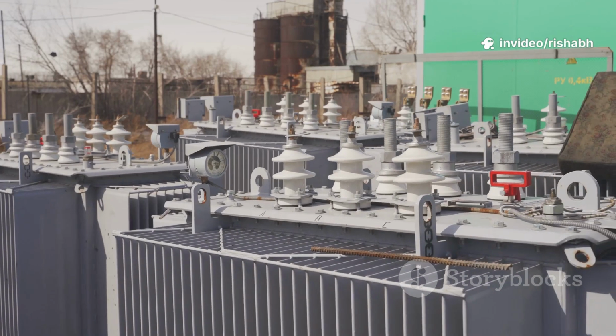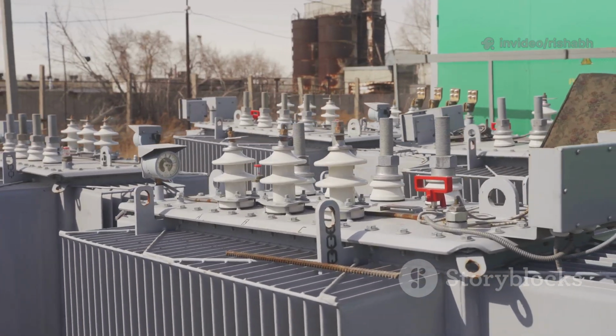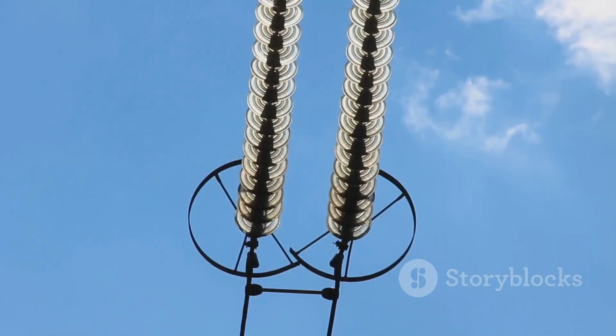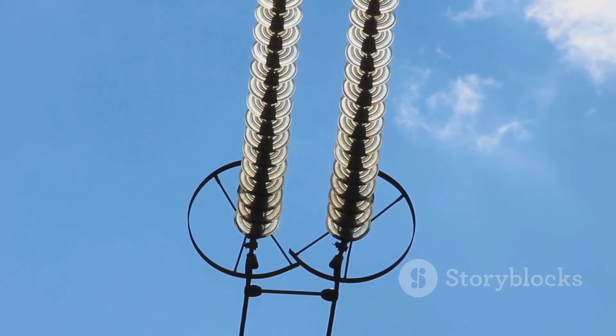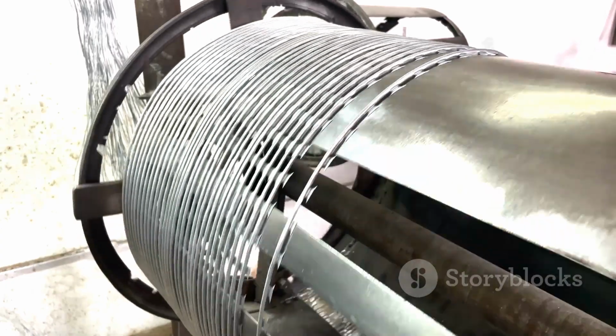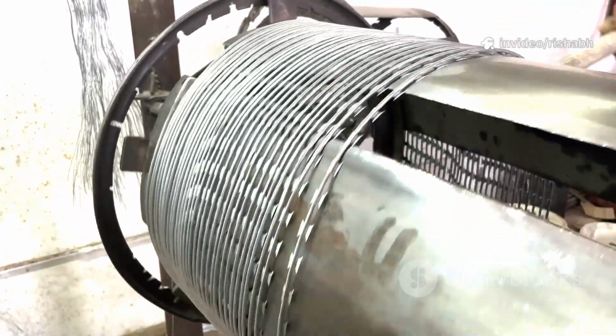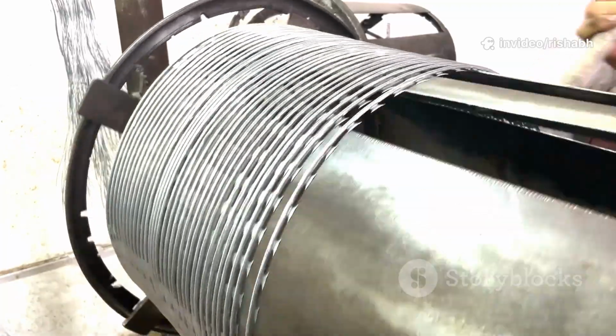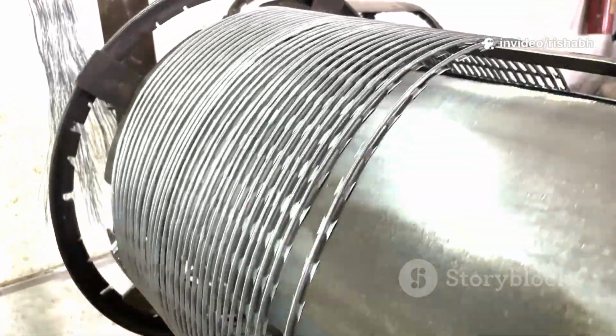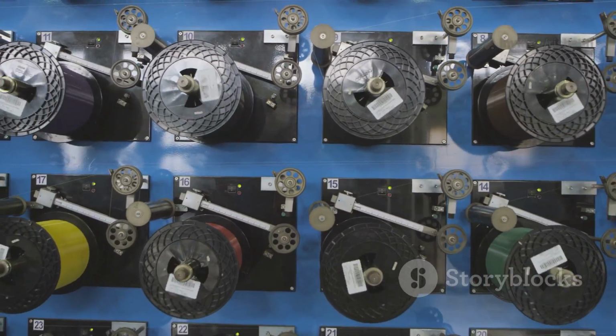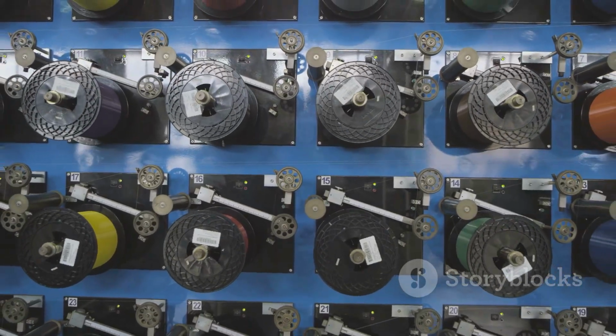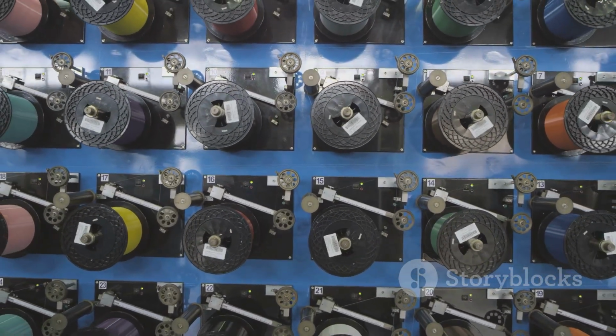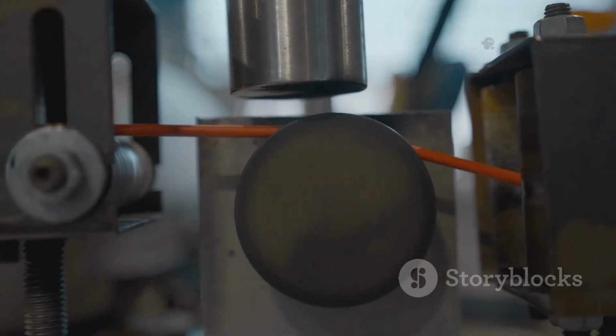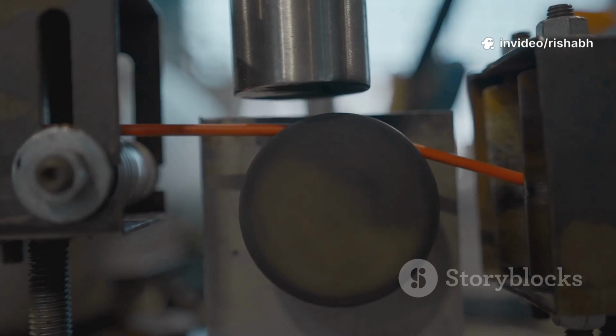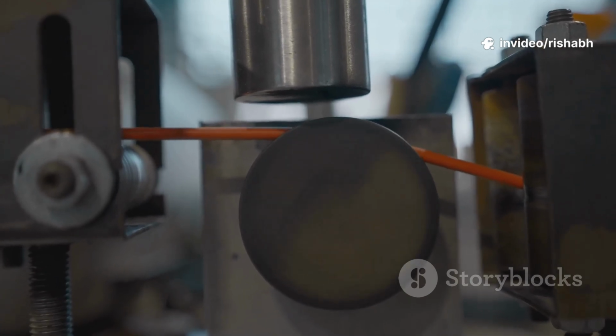These complex arrangements are designed to distribute voltage stresses evenly, especially during transient events like lightning strikes. The craft of winding a transformer is a blend of precision, engineering, and artistry, ensuring that these coils can withstand the electrical and mechanical forces they will endure for decades of service. It is a dance of copper, paper, and oil, choreographed by the laws of electromagnetism.